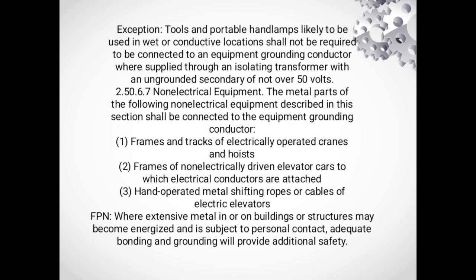2.50.6.7 Non-electrical equipment. The metal parts of the following non-electrical equipment described in this section shall be connected to the equipment grounding conductor. Number 1. Frames and tracks of electrically operated cranes and hoists. Number 2. Frames of non-electrically driven elevator cars to which electrical conductors are attached. Number 3. Hand-operated metal shifting ropes or cables of electric elevators. And where extensive metal in or on buildings or structures may become energized and is subject to personal contact, adequate bonding and grounding will provide additional safety.